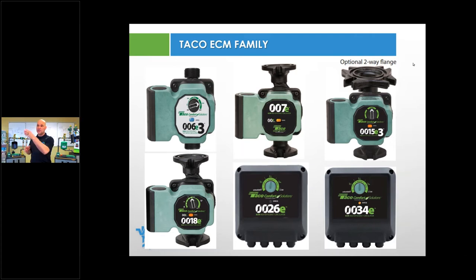And if you need to make adjustments, you can go right there to the little knob on the back of that 0018E, make your adjustments and dial it into your system so that you're hitting the proper system curve and performance curve of that circulator.